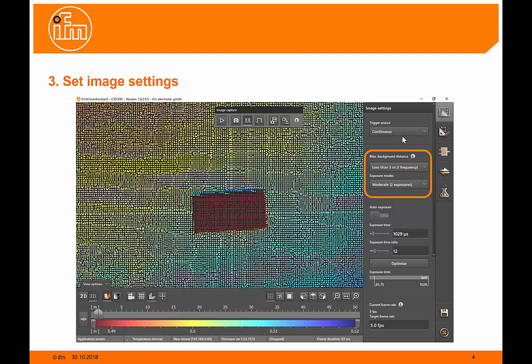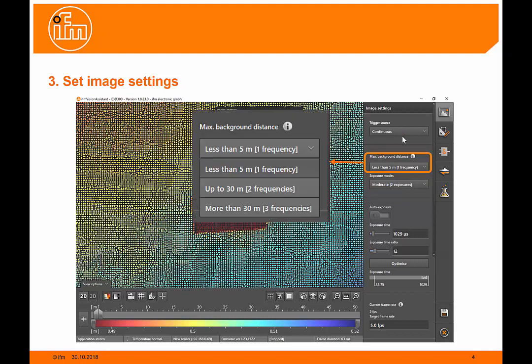Here we set the maximum background distance. This is the maximum distance to the object that we can see. If we're looking above a conveyor, for instance, and it's two meters away, we can set less than five meters. But if we're looking into the open and it can see quite a distance, we'll need to set it further, for instance, more than 30 meters.